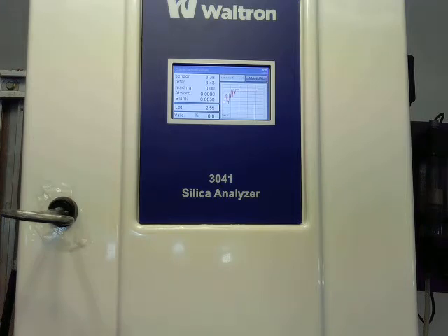So now we can probably hear and see that reagent number 2 is being added. Again, I want to have about another minute of mix before we update our reference value. Again, that's our before reading. If there was any dirt building up on the flow cell or a little bit of turbidity in the water, that would all be taken into account at this stage.